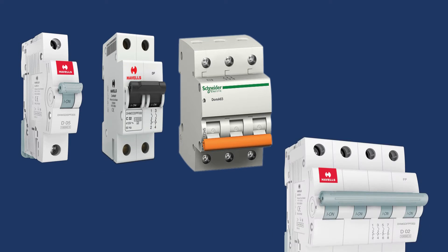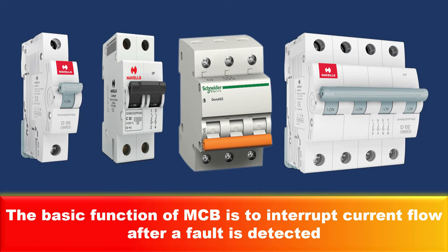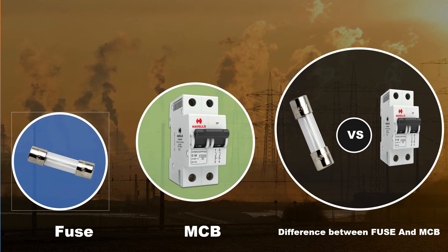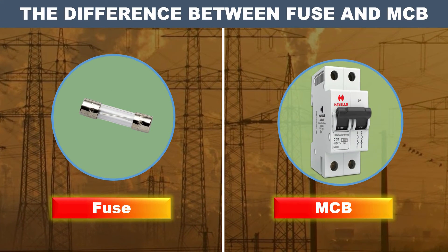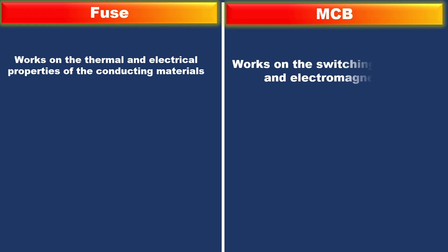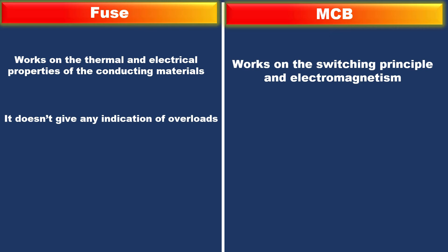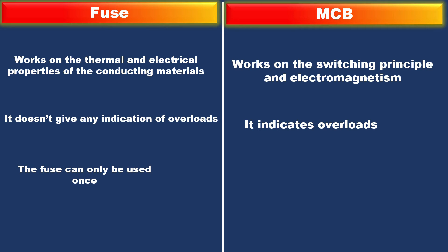Now, what is the difference between a fuse and a circuit breaker? A fuse works on the thermal and electrical properties of conducting materials, while an MCB works on the switching principle and electromagnetism. A fuse does not give any indication of overload, while an MCB indicates overload. Also, a fuse can only be used one time, whereas a circuit breaker can be used many times.